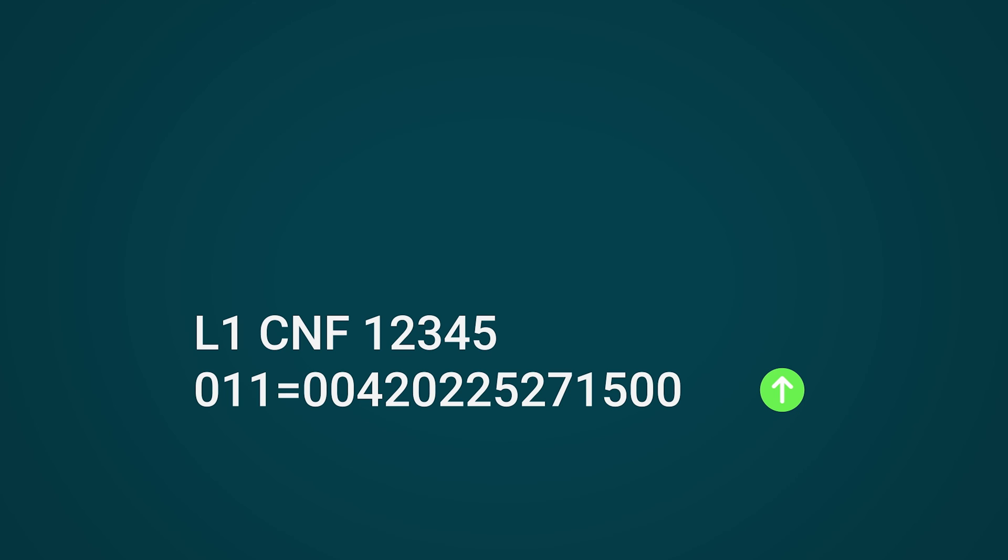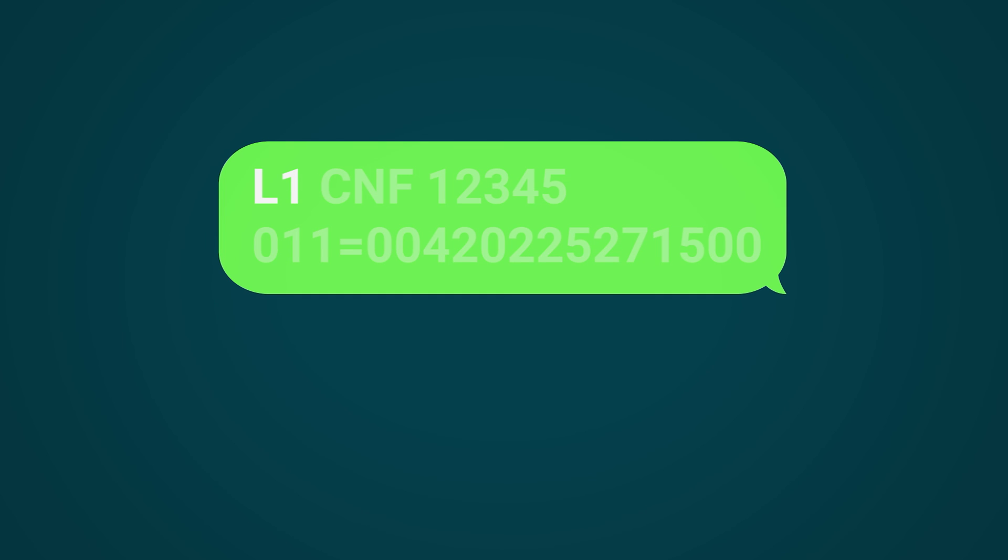this is the format of the SMS for configuring alarm calls. L1 defines the product, Lift 1. CNF stands for configuration. 12345 is the default service password you need to know to configure the device. Make sure you change this. Instructions are in the manual. 011 is a parameter for setting up the first number that should be called after pressing the alarm button, followed by the telephone number itself.